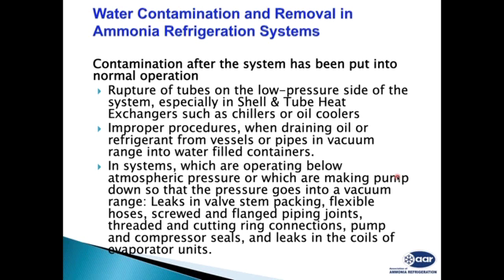Consider a case when we are charging ammonia into the plant. The ammonia cylinder pressure is higher, so when we connect it to the system, the ammonia starts passing from the cylinder to the plant. When both pressures equalize, our operator sees that there is some water in the cylinder. He has to elevate the cylinder so that it can drain the remaining ammonia into the system. But what he does is tilt the cylinder by 180 degrees. So whatever water was at the bottom of the cylinder, 100% of it enters our system, and that water starts coming in.